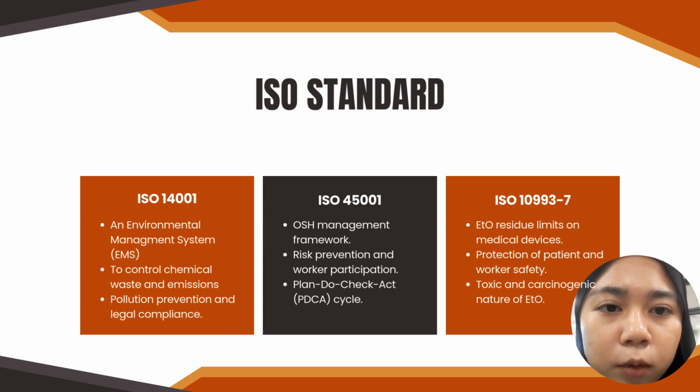So next, we move to ISO 10993 Part 7, which is ethylene oxide residue control. So ISO 10993-7 is a standard that specifies acceptable limits for ethylene oxide residues remaining on the medical devices after sterilization. This standard is crucial because ethylene oxide is highly toxic, flammable, and classified as a Class 1 human carcinogen. BBRAUN uses this standard to validate its sterilization and aeration processes, ensuring that residual ethylene oxide levels are reduced to safe limits before products are released for use.